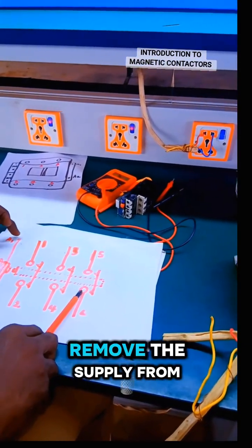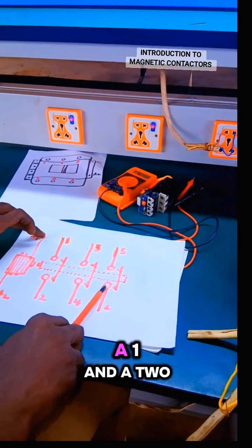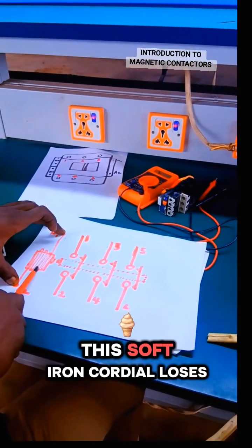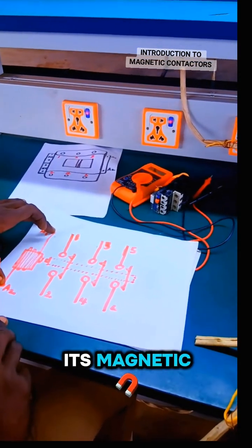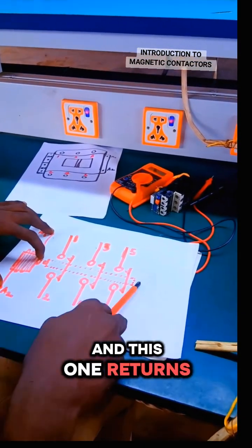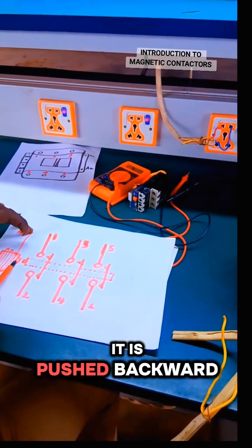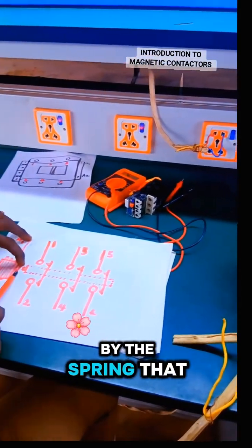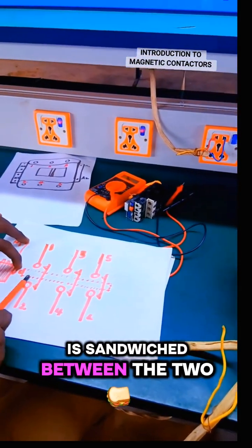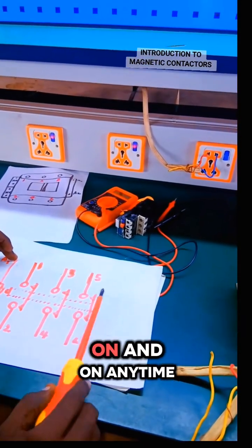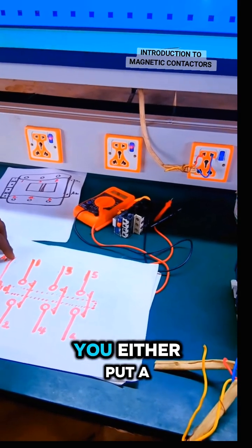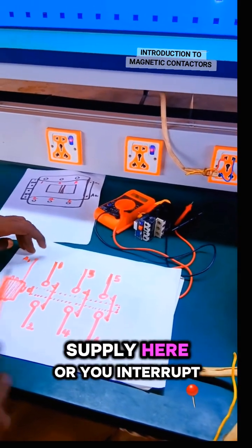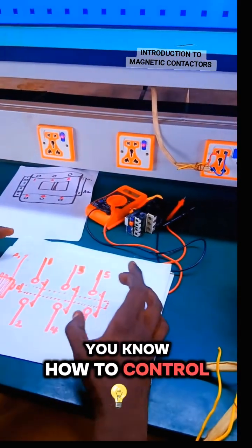And the moment you remove the supply from A1 and A2, this soft iron core here loses its magnetism, and this one returns to its initial position. It is pushed backward by the spring that is sandwiched between the two. And this continues on and on, anytime you either put a supply here or you interrupt the supply. You know how to control your contactor.